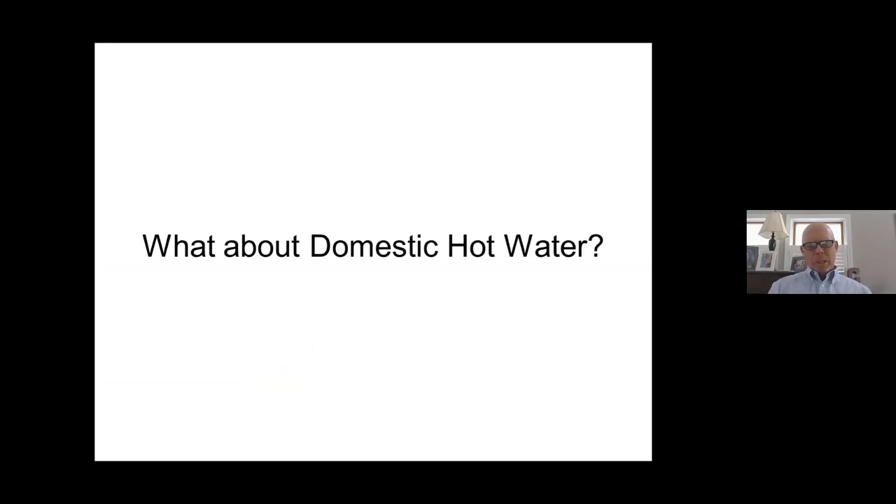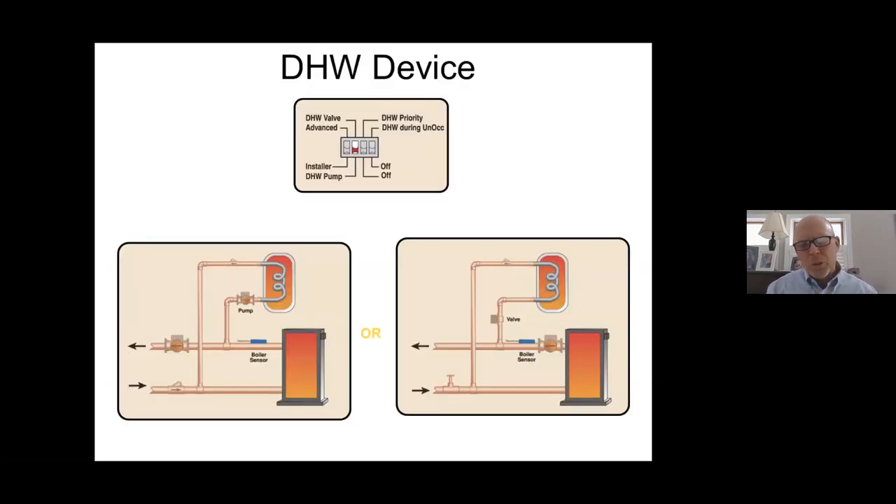A common question: I have an indirect water heater — how do I recover it while doing outdoor reset? All controls, whether on the boiler or a separate tekmar control, acknowledge that when you have a domestic hot water call — through a sensor or aquastat — they'll temporarily override outdoor reset and drive the boiler to a predetermined temperature, typically 170 to 180 degrees, to recover the tank via the coil. And you can do it with an individual pump — which is 90% to 95% of applications — or a zone valve, with priority control options.